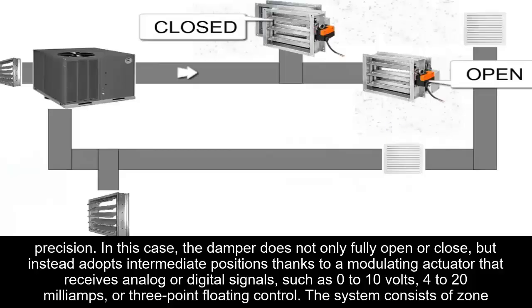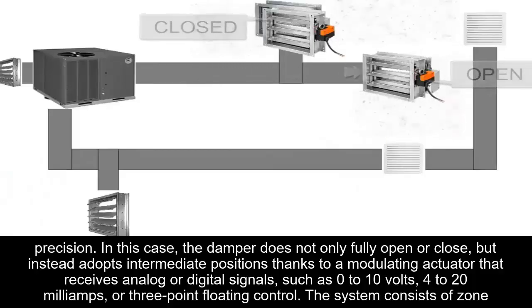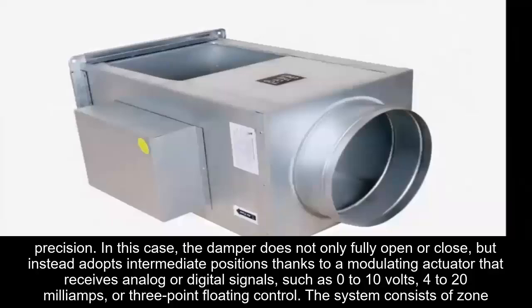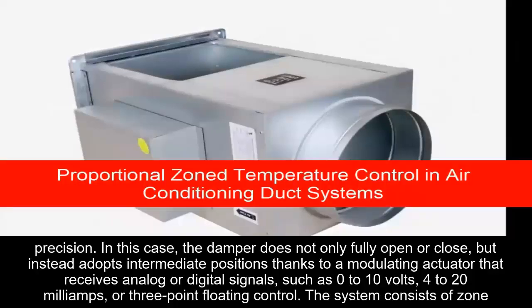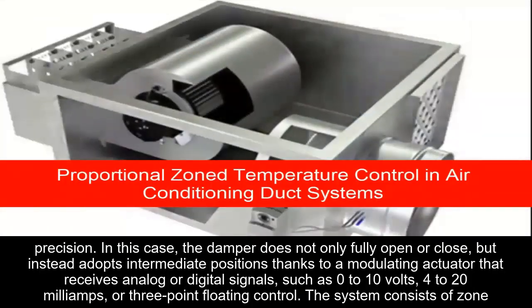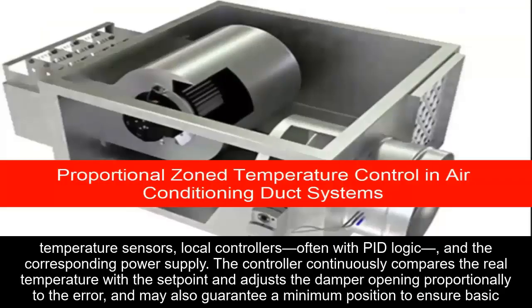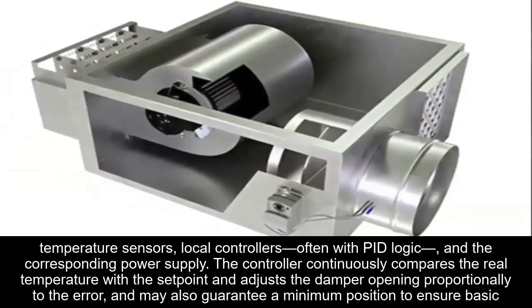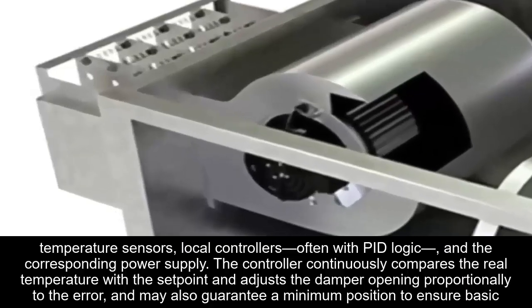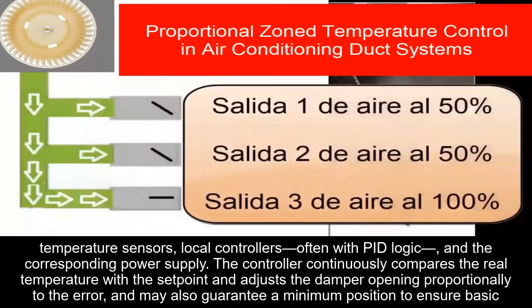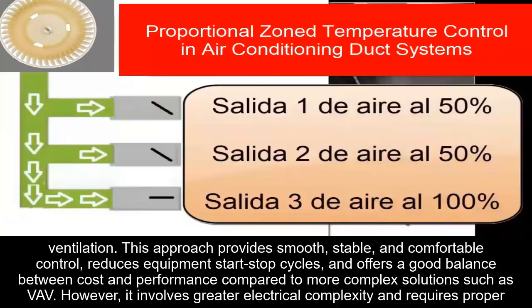In this case, the damper does not only fully open or close, but instead adopts intermediate positions thanks to a modulating actuator that receives analog or digital signals, such as 0 to 10 volts, 4 to 20 milliamps, or 3-point floating control. The system consists of zone temperature sensors, local controllers, often with PID logic, and the corresponding power supply. The controller continuously compares the real temperature with the set point and adjusts the damper opening proportional to the error, and may also guarantee a minimum position to ensure basic ventilation.